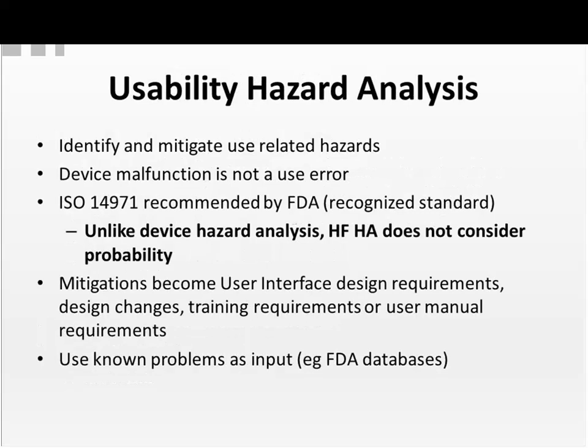We conduct a usability hazard analysis. The objective is to identify and mitigate use-related hazards. Keep in mind that a device malfunction, a failure of the device, is not a use error. The FDA recommends that you use ISO 14971 to do the hazard analysis. It's an FDA-recognized standard.